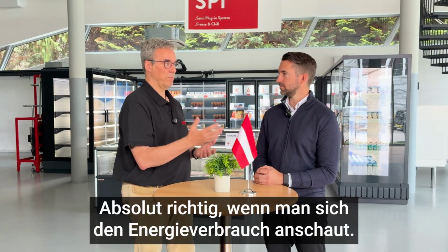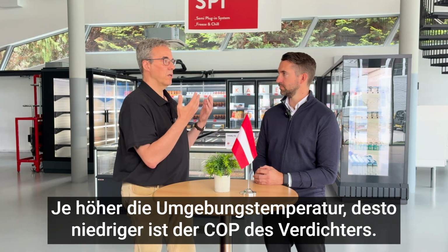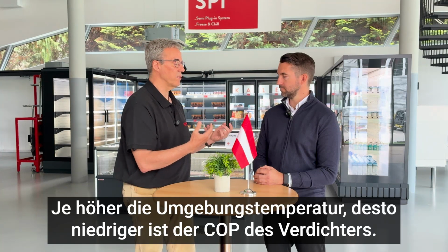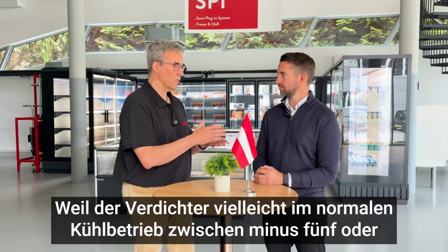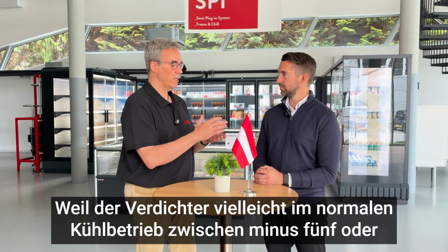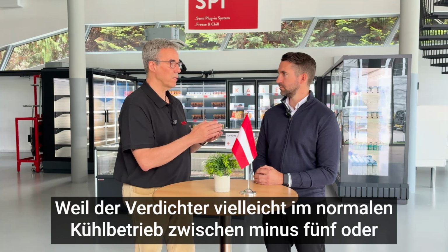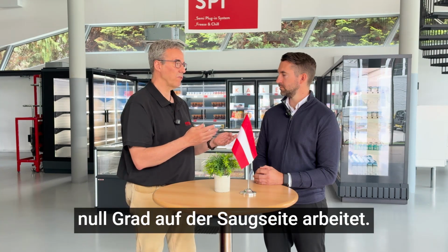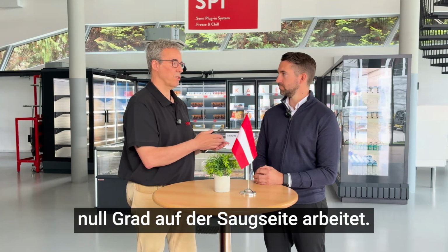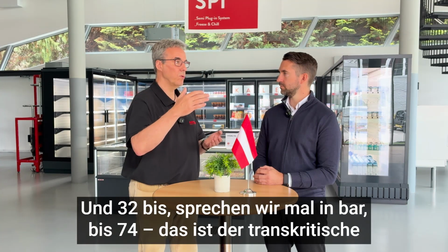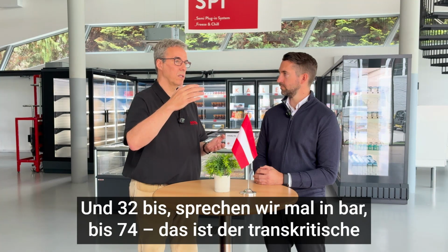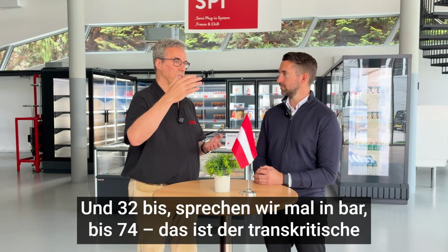The higher the ambient temperature, the lower the COP of the compressor, because the compressor is working between maybe normal cooling of -5 or 0 degrees on the suction side, and 32 up to, let's talk about bar, up to 74.